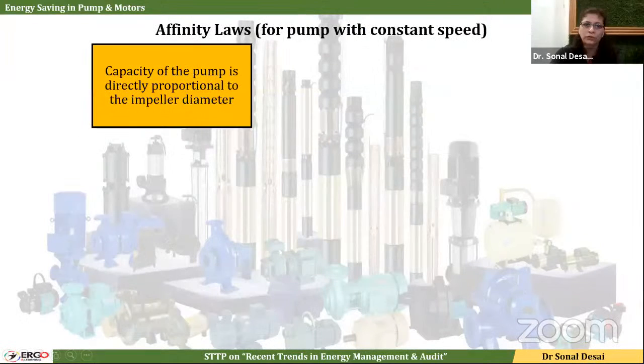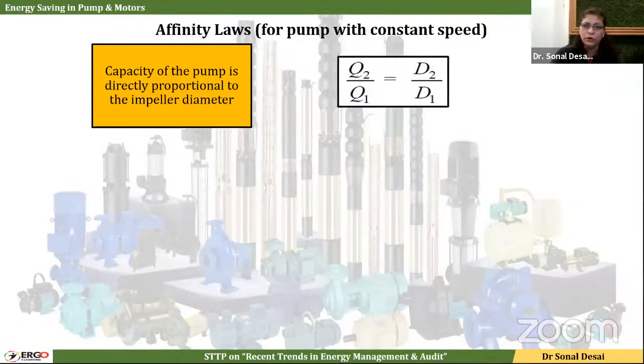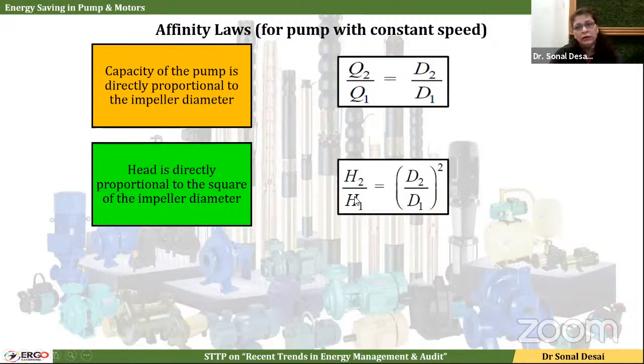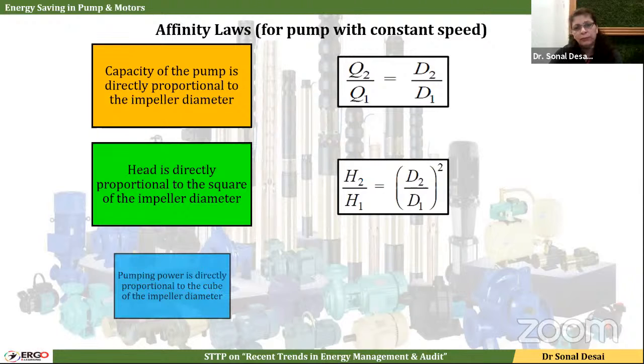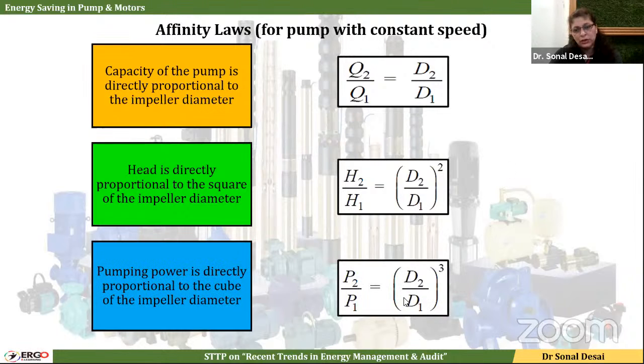So let us have a further look at the affinity law for constant speed and varying diameter. When we change the diameter, the flow will decrease in direct proportion. Head will decrease in the power 2, and power will decrease in the power 3. So if we reduce the diameter, there is less change in head, but there is a subsequent change in power. So when we talk of making a pump more efficient, the foremost method is to change the diameter.